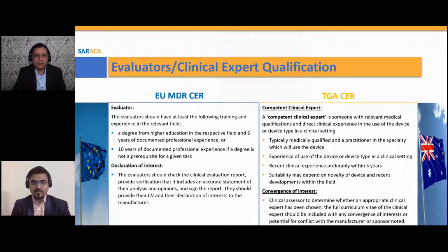The practitioner must have some kind of specialty or experience with the device and its use. It must be experienced in the use of the device in a clinical setting, have recent clinical experience, preferably within the last 5 years, and suitability may depend on the novelty of the device and recent developments within the field. That's a pretty strict definition of a clinical expert.